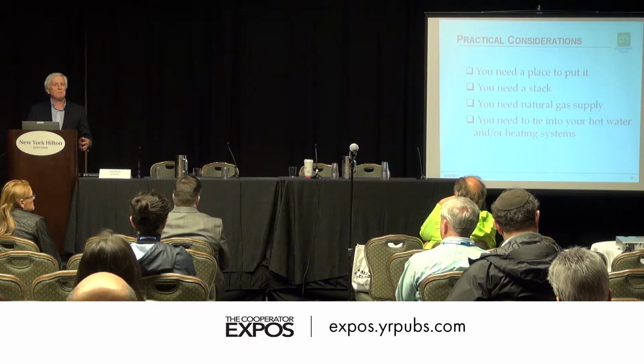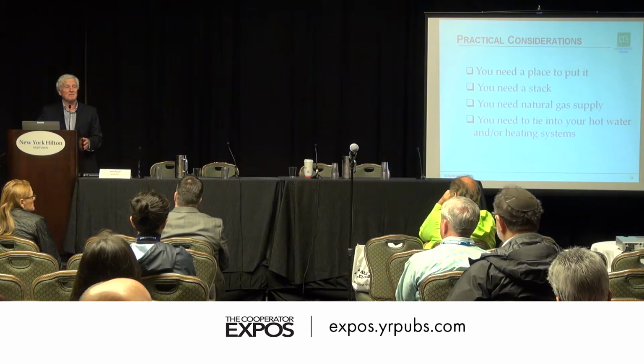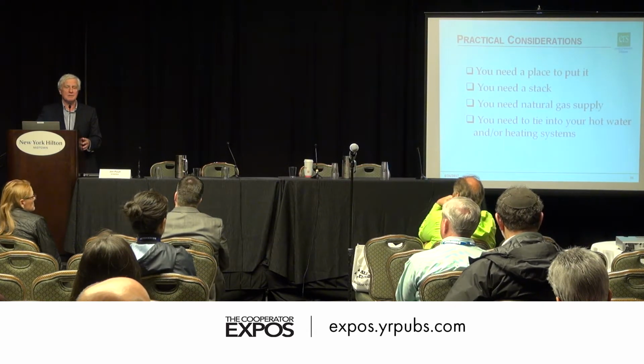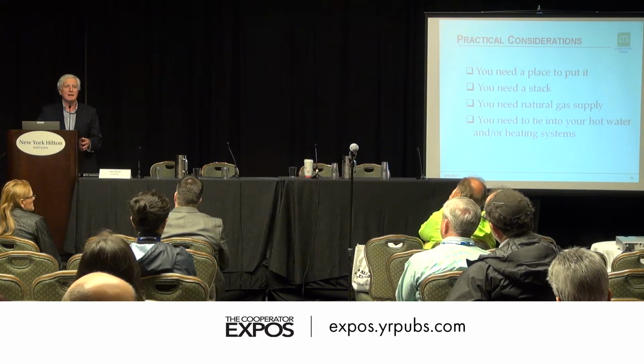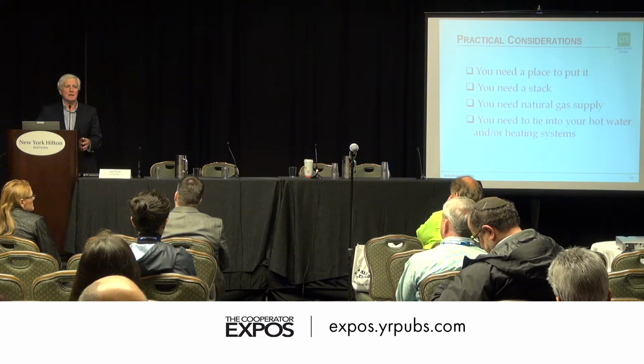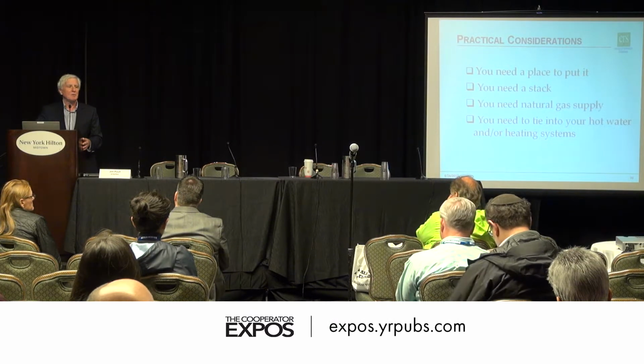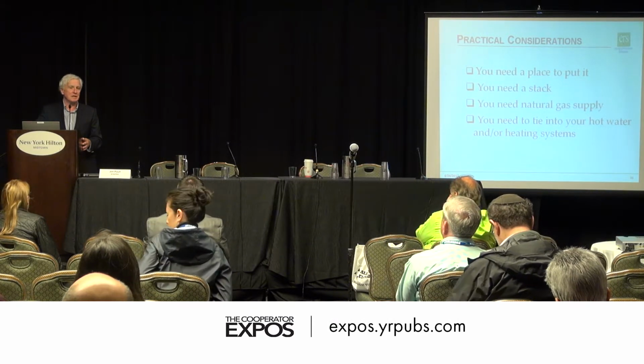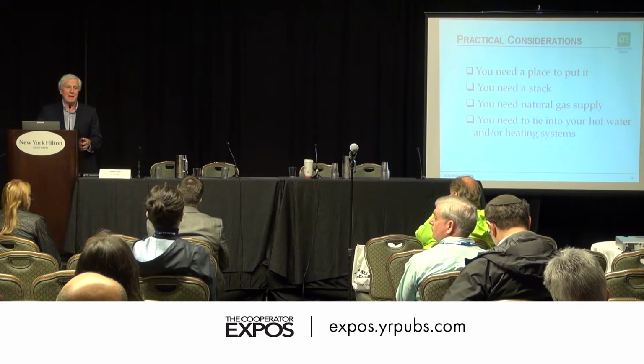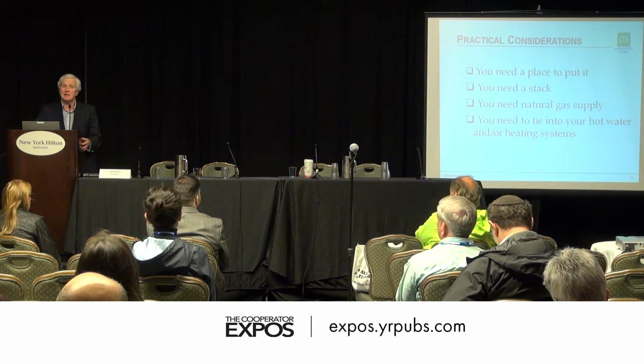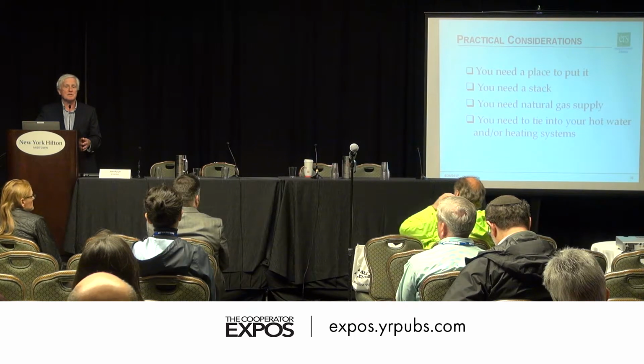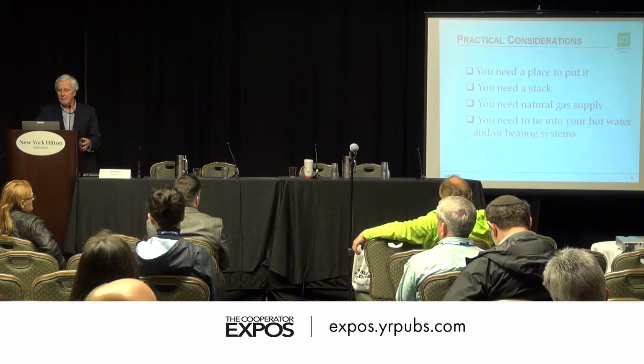You need a natural gas supply - enough gas on the street, with sufficient flow and pressure, to meet the CHP's needs. Your natural gas supplier will help you determine that, and you'll need to have the gas routed to the location in the building where you're putting the system. If it happens to be on the roof, you might have to run a gas line up there, so there are some considerations there.